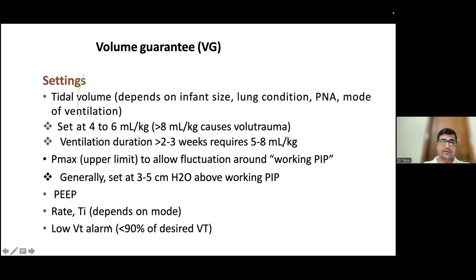So coming to troubleshooting, the most important troubleshooting is the alarm for low VT alarms. It's very problematic and can create a lot of noise in the NICU. So you have to remember that there are some correctable causes which lead to these low VT alarms, like if there is a worsening ET leak.